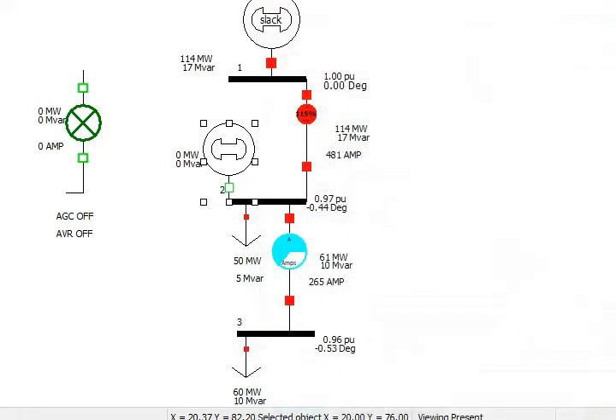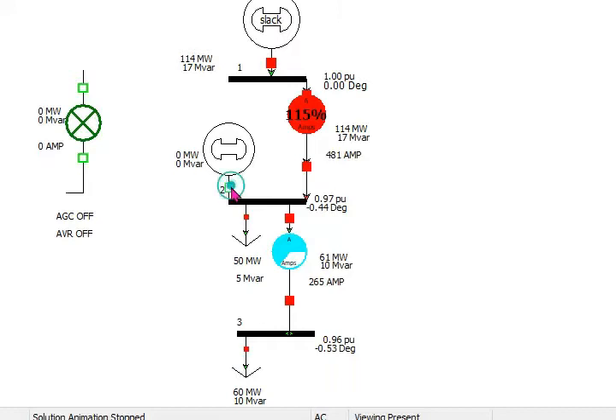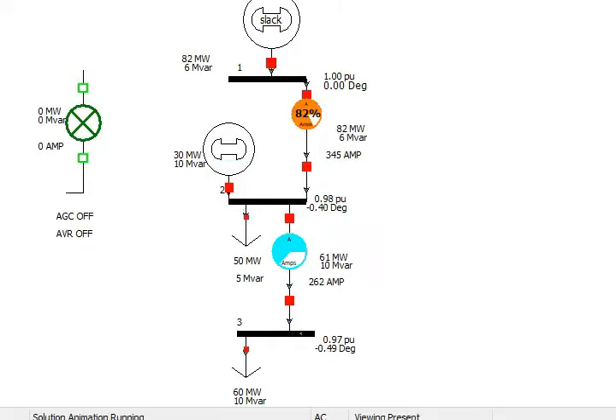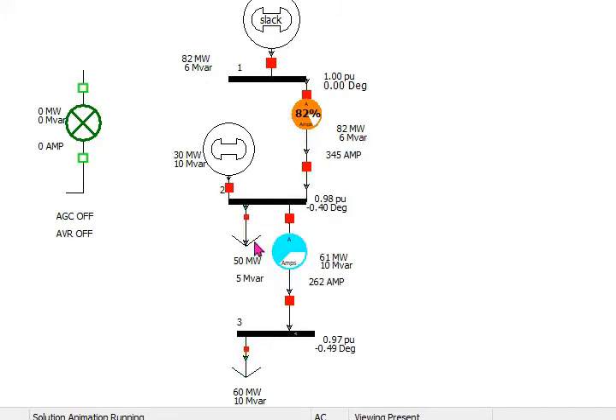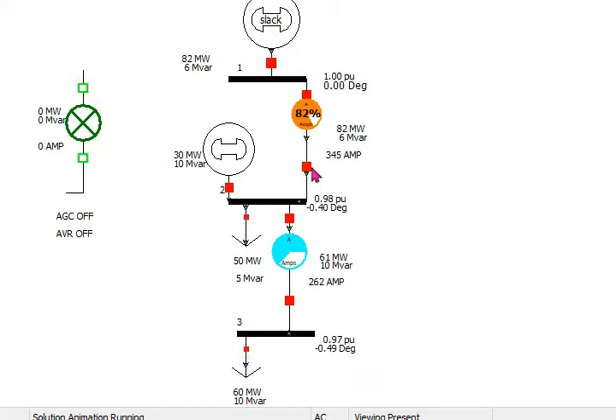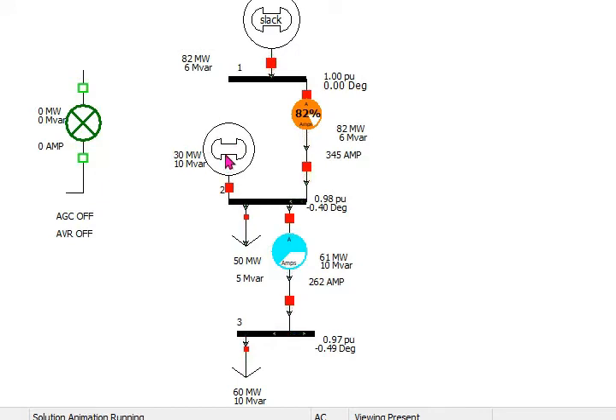So if you take in service this DG and click on it, you can see that the first transmission line is reduced to 82 percent. Previously 114 megawatt was there, and this second transmission line is also not overloaded. The power flowing through this transmission line is reduced, and 30 megawatt is provided by this DG to the load.